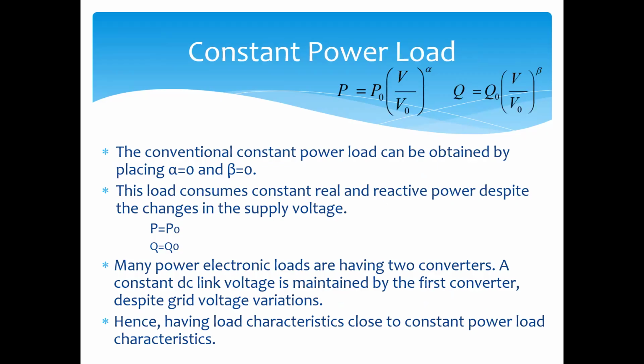If we place alpha equal to 0 and beta equal to 0, the constant power load model can be obtained. Once we place 0 there, this whole component becomes 1. Constant power means whatever system voltage we apply, it consumes constant power. It doesn't change its power consumption. That's why it's called constant power. Its power consumption is not dependent on the system voltage. So P is equal to P naught, Q is equal to Q naught.